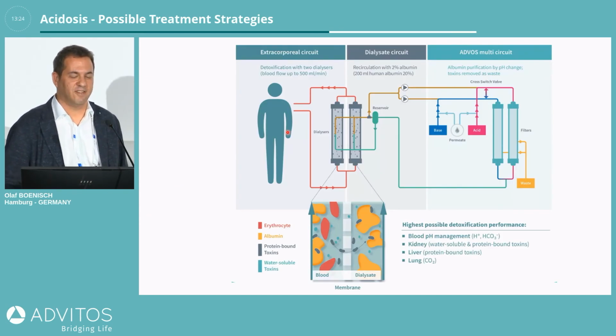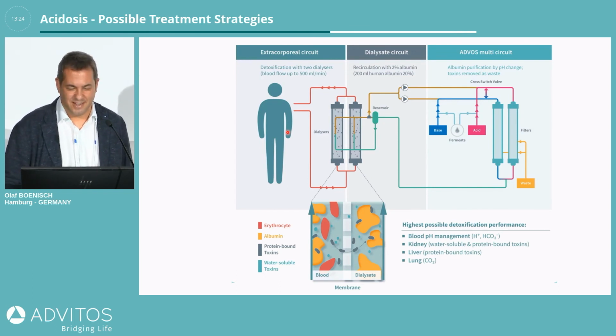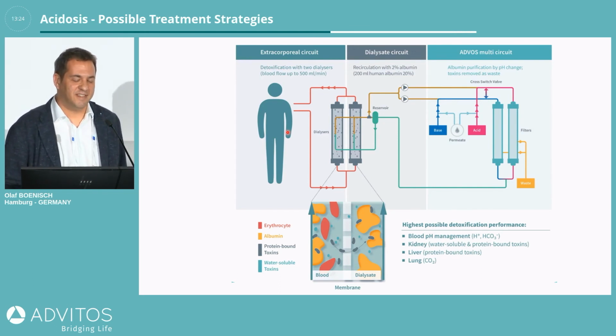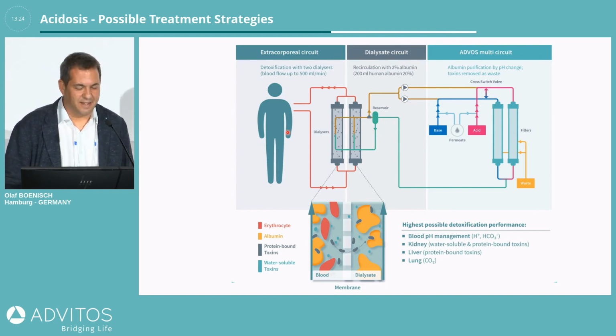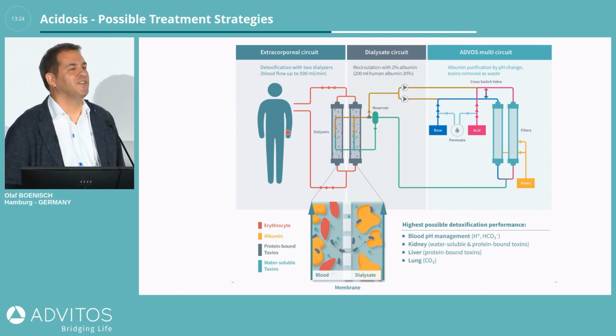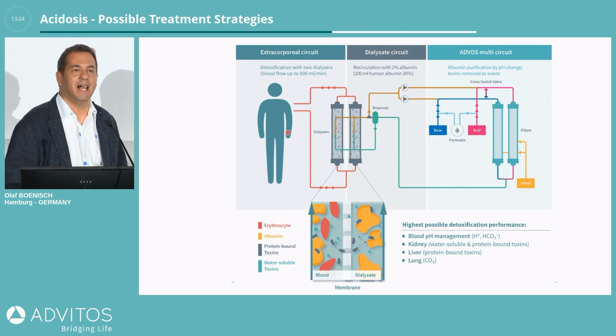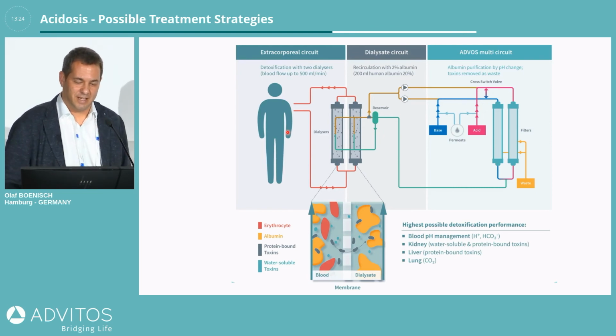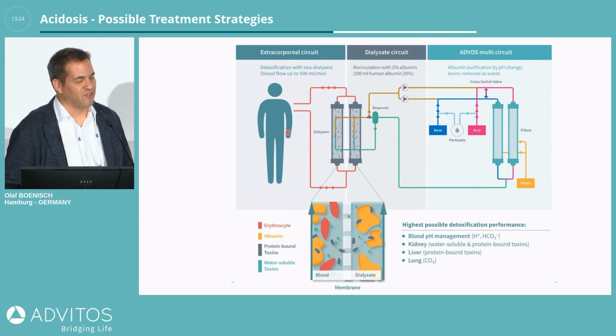We have an extracorporeal blood circuit, as in every dialysis system. We have a dialysate circuit. And the special feature in ADVOS is that albumin is added to the dialysate. We are talking about this later. And then this is a special feature of ADVOS.